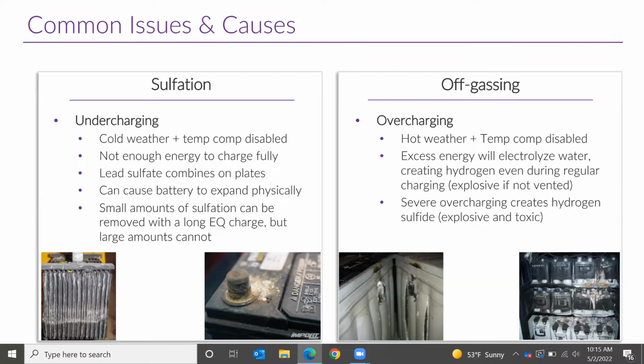Now you may also have the issue of off-gassing. So if you're smelling, I hope you are not smelling sulfur, but if you're smelling something that's coming from your lead acid battery bank, first off, note that they're being overcharged and you should turn the charging voltage down. Or maybe in hot weather, maybe you've forgotten to enable temperature compensation, which is going to automatically turn that charging voltage down in high temperatures. So any excess energy will electrolyze the water in the electrolyte and cause this to turn to gas. This hydrogen itself is not toxic, but it's explosive if it's not vented.